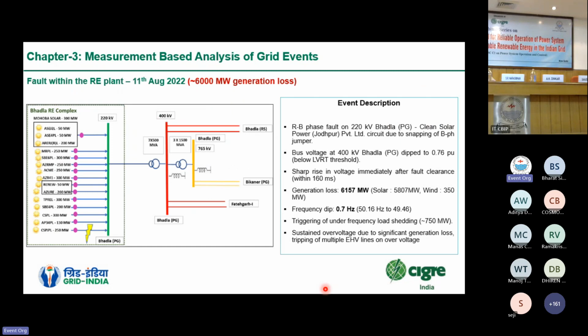So we have covered one event of each type in this presentation. Coming to the first category, fault within the RE plant. This event took place on 11th of August, where we lost 6,000 megawatt of generation in Rajasthan RE complex. There was a phase-to-phase fault in a solar plant connected at the Bhadla PG station.